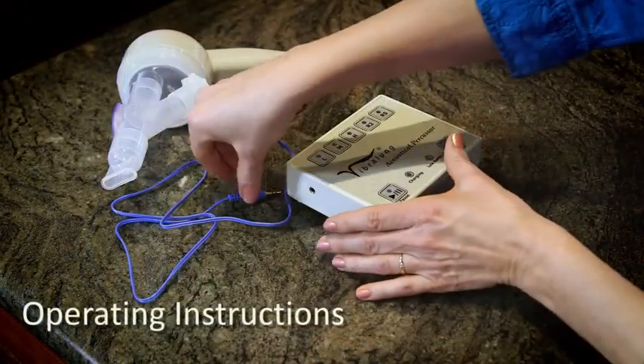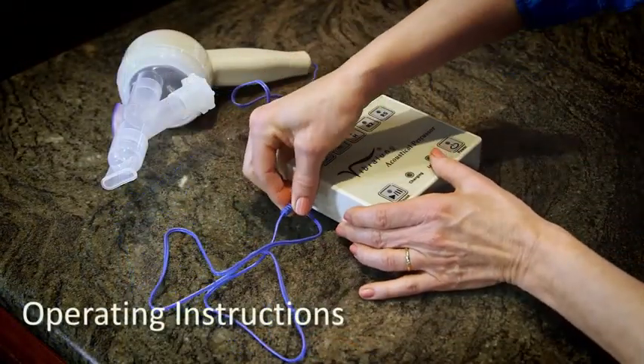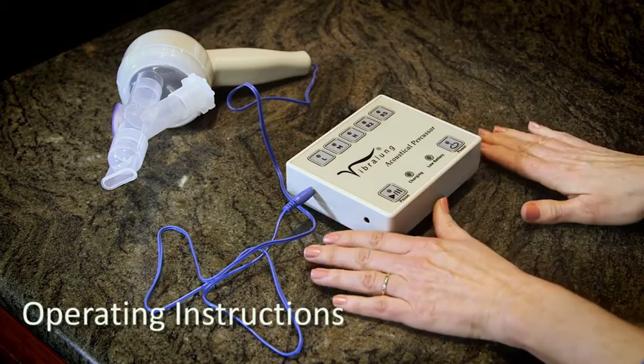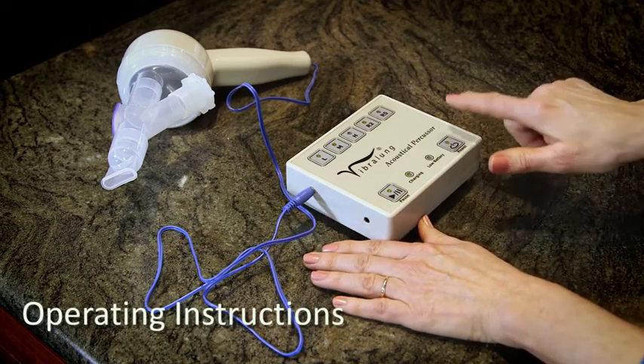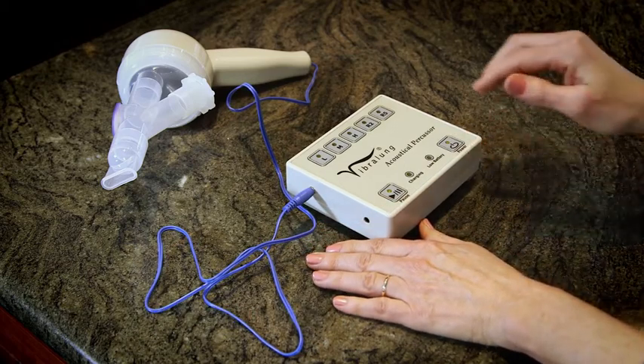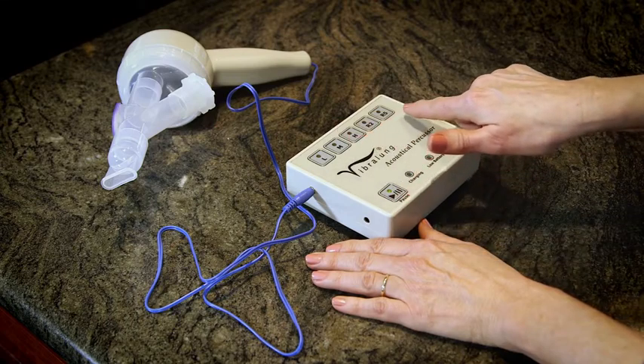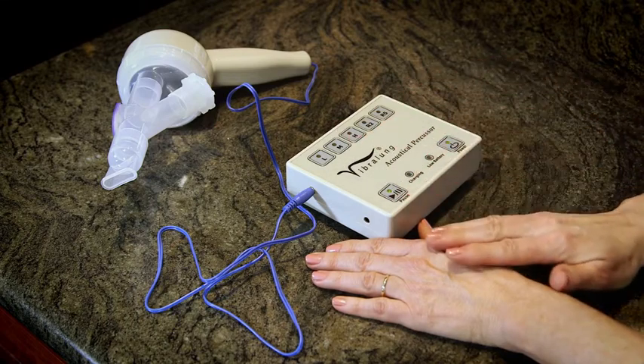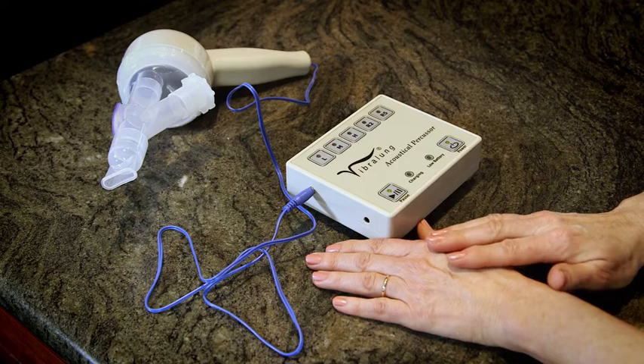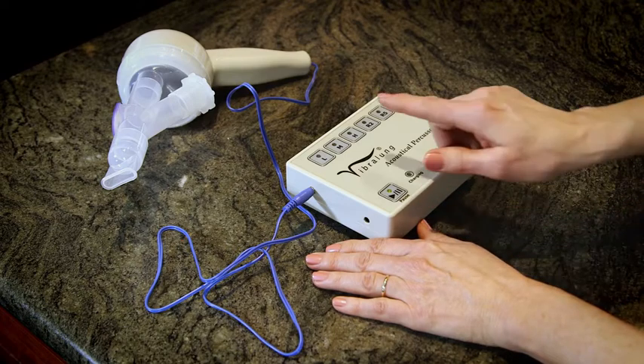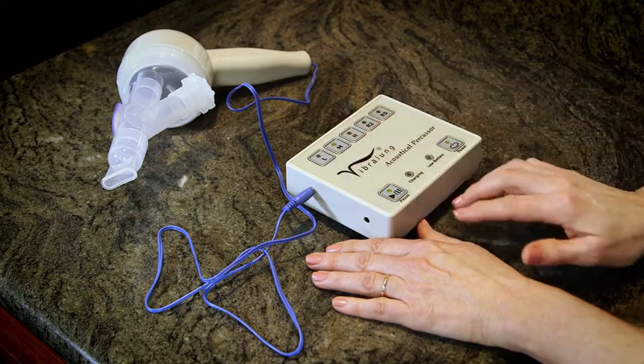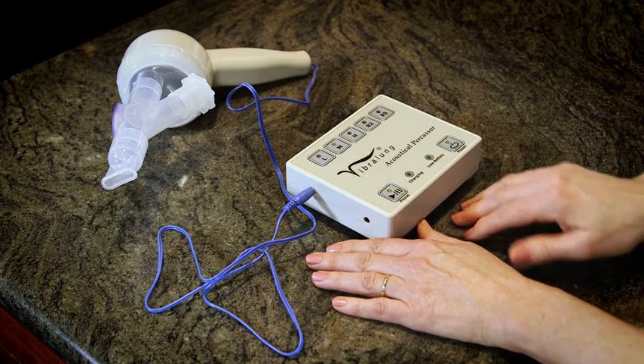Plug the handheld transducer into the treatment control unit. Press the power on-off button. Press one of the 5 setting buttons in the top row corresponding with prescribed treatment. The selected button will illuminate, for example, M for medium frequency treatment. Press the play-pause button to activate the device at the selected setting.